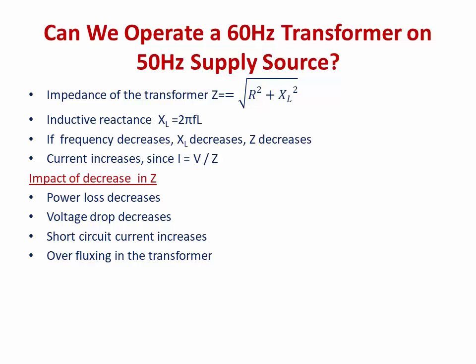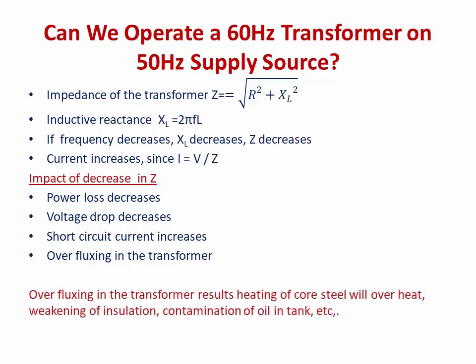What happens when over-fluxing occurs in a transformer? When there is over-fluxing, it creates heating of the core steel, weakening of insulation, contamination of oil in the transformer tank, and several other harmful effects. Hence, a 60 Hz transformer is generally not operated on a 50 Hz supply source.